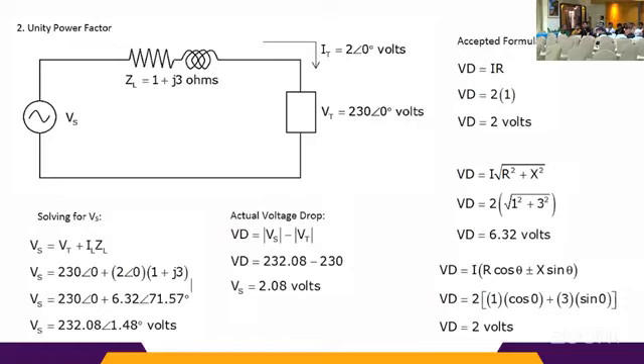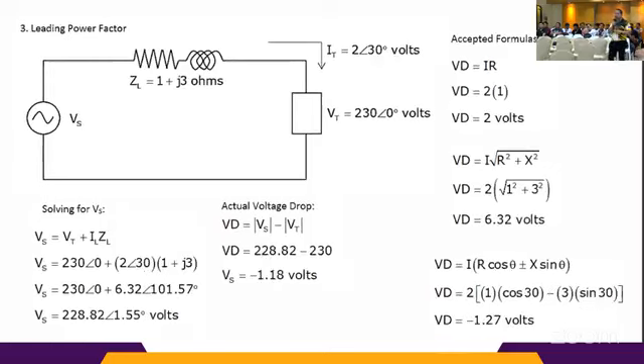Just recall, no? The next is for the leading power factor. Now for the leading power factor, next slide please. For the leading power factor, of course, our current is leading, nasa taas. So the angle is 30 degrees. Okay? So same formula. So we come up, the voltage drop is negative 1.18 volts. Then another formula on the right side. Then down there, voltage drop is negative 1.27 volts. That is for leading power factor. So we have to use a negative sign.